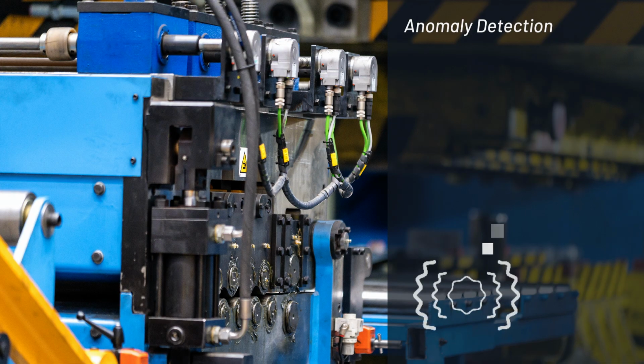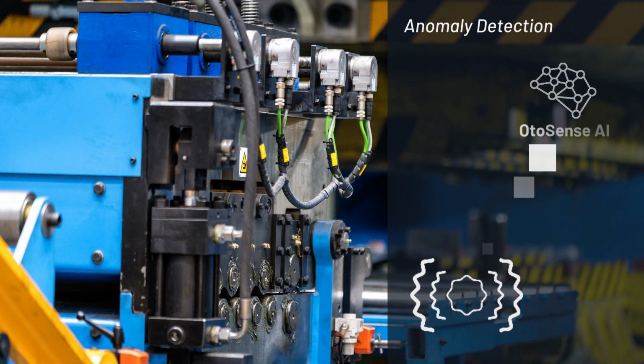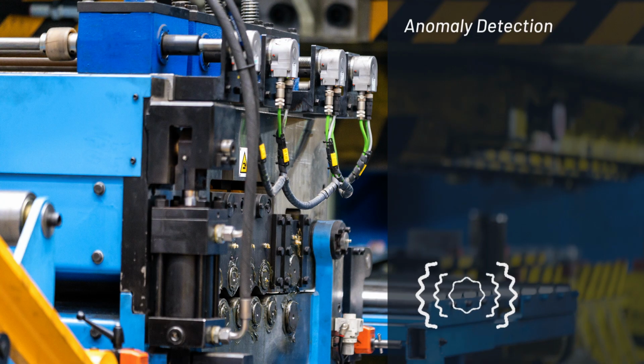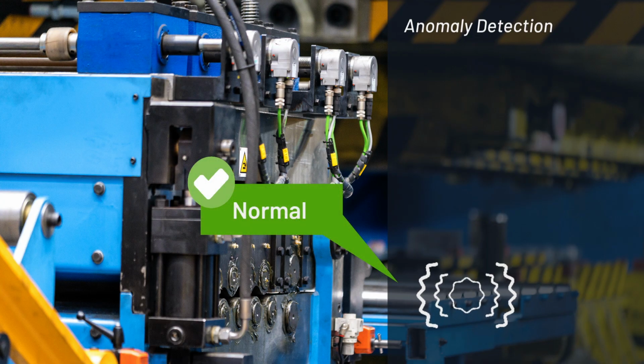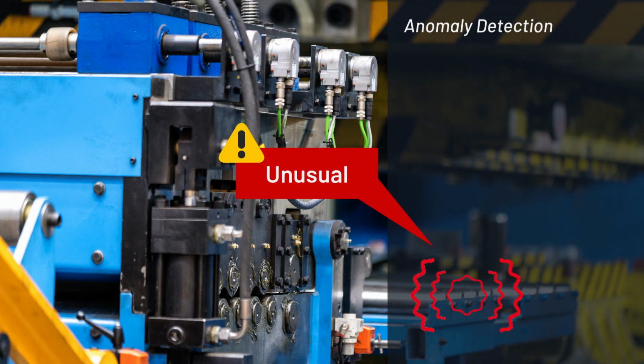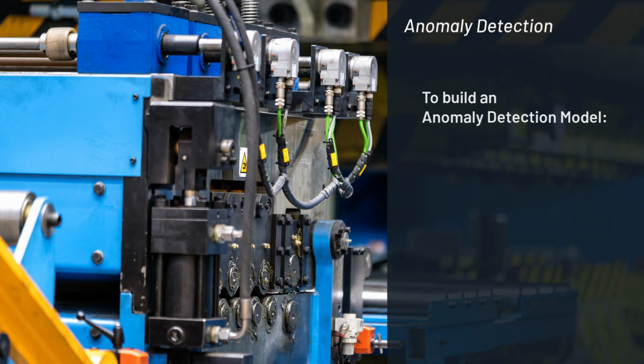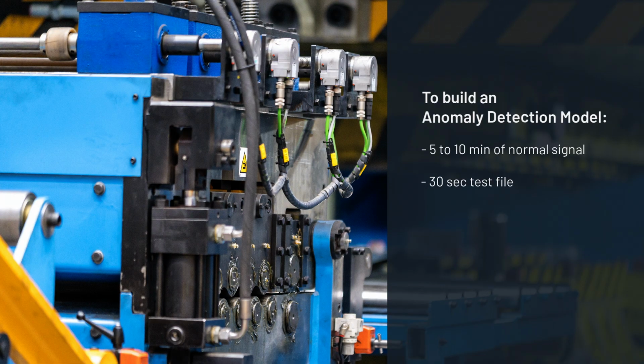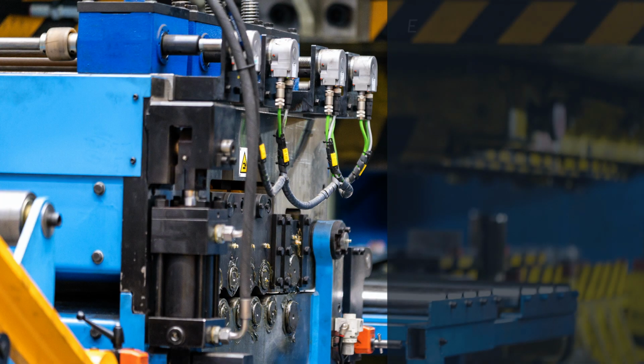With the anomaly detection model, OtoSense learns how a machine behaves under normal conditions. When it has finished learning normal condition behavior, OtoSense can then let you know when it detects something unusual or abnormal compared to the normal signal it has learned. For this type of model, you will need to collect 5 to 10 minutes of normal signal on your machine and also build a roughly 30-second test file where you will put either just the abnormal signal or a range of both normal and abnormal signals.